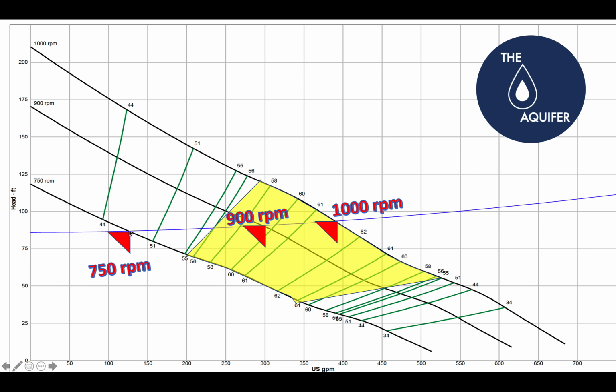And one thing I want to point out is, as I mentioned before, this is almost all static head. We have very little frictional head in this very short force main. And these are the ones that you've got to be careful about, because this is a situation where the shape of your curve is very flat, and so it's easy to drop right out of the preferred operating range, very easily by turning the pumps down. Sometimes you'll see curves that have a real steep shape, and it's not as concerning. But this is the situation where this could happen, and we've actually almost dropped out of the allowable operating range.